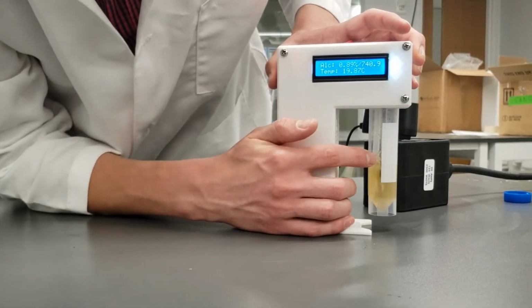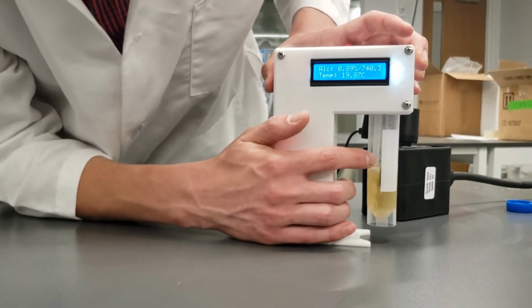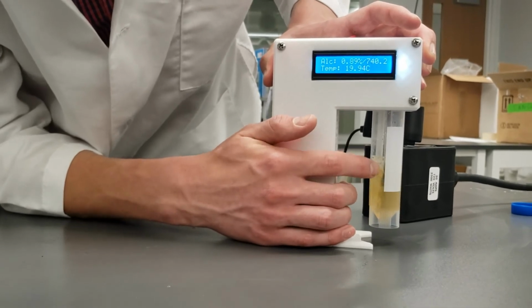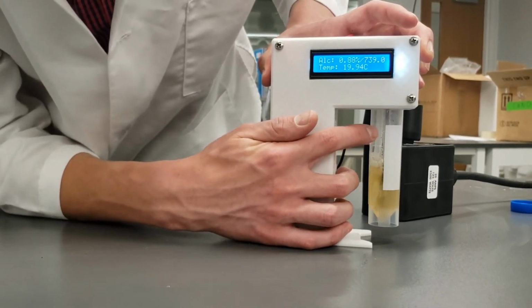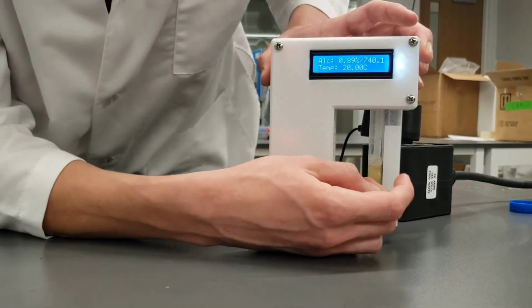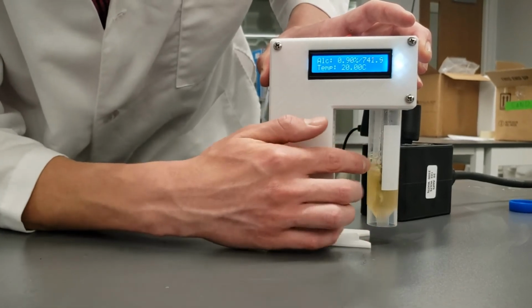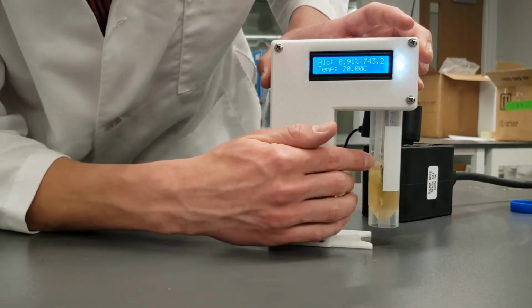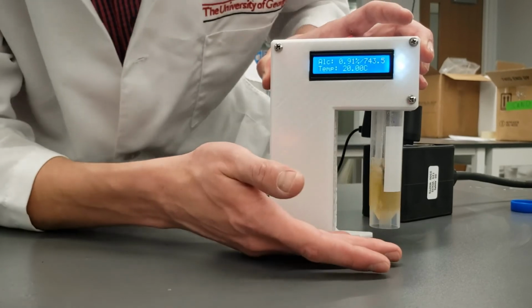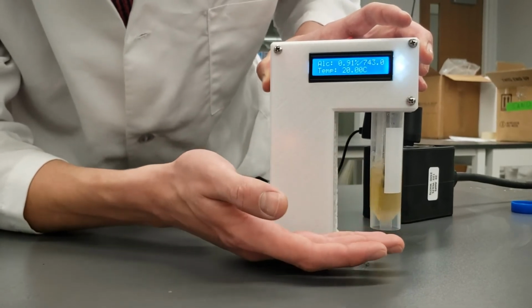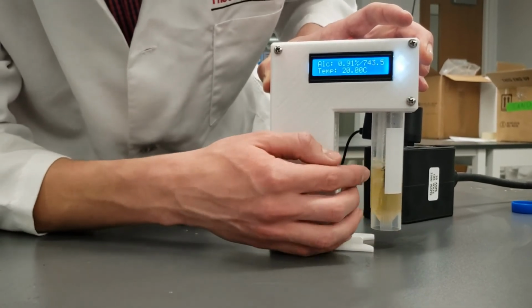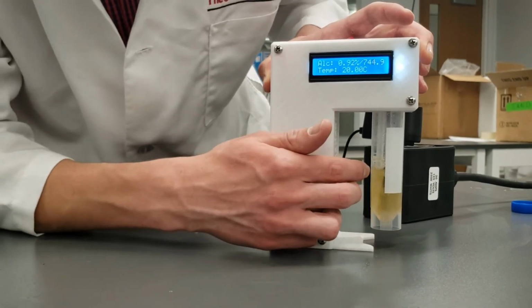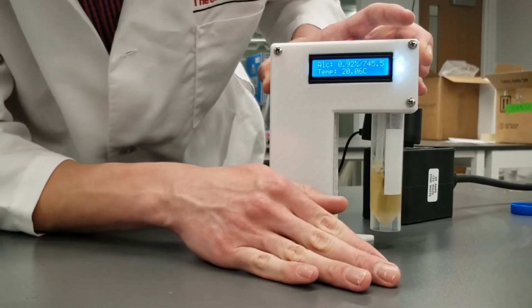Again, with the foaming of the sample, just be very careful. Watch the foam that's rising in the sample as you screw it in, and if there is excessive foam for whatever reason in the kombucha that you're testing, you can add about 1 or 2 milliliters of some sort of neutral oil like vegetable oil, or if you have it, you can add a single drop of anti-foam, and that will completely fix the issue.